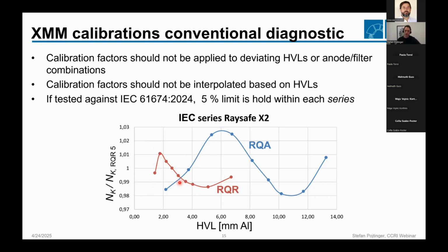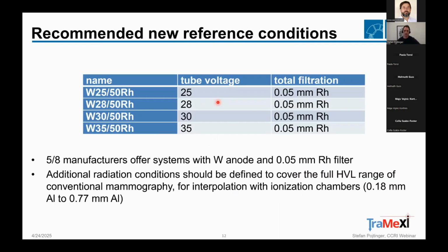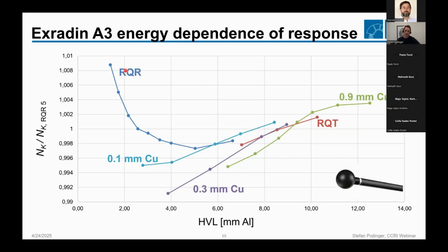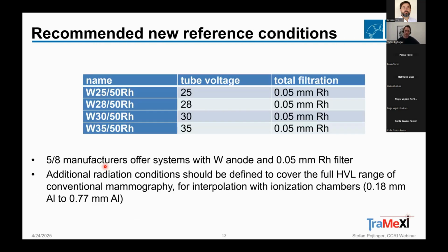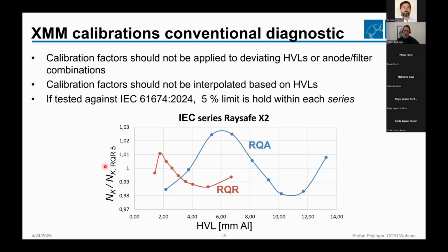And another thing that is really different is that the curve is not so nice looking like for the ionization chamber. For example, if I go back here for the Raysafe X2, you could kind of interpolate, for example, between RQR2 and 6 or so, and you would move closer to the calibration coefficient you actually want to have. But for some XMMs in some scenarios, that can be a horrible choice. For example, here for RQR, if you use RQR2 and RQR6 for interpolation, you will make a huge mistake. And because this will always depend on the algorithm, the diodes, and the really individual detector, we don't recommend to do any interpolations of calibration factors for XMMs based on HVL.